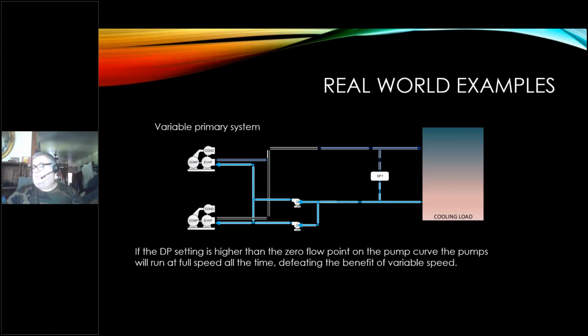And so some strategies will say, okay, change the setting on the pressure differential. Some of them will set it to a fixed setting and just operate on that, where the pump speed will change as long as I maintain a constant. That's not good, because you're basically saying that the resistance to flow is going to stay the same, and you change the speed of the pump. That means you're keeping the horizontal line constant all the time and just riding that pump curve back on the flow. Well, you can save a little bit, but not a lot.